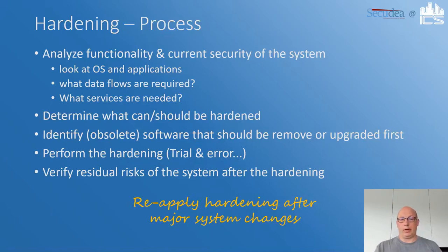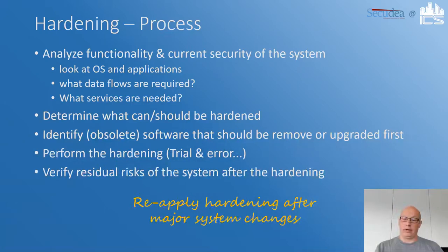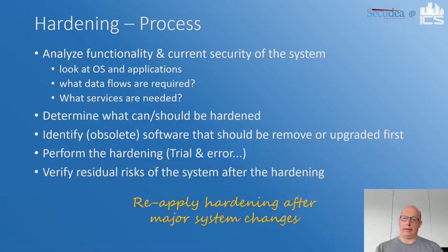After you do the hardening and everything is running, first verify the functionality of the system. Then it's also key to verify residual risks after hardening to make sure the system is as secure as possible and to identify what can be done with remaining risks. Whenever there are major system changes to the hardened system, verify whether hardening needs to be reapplied, because installing patches or application upgrades may require settings to be reapplied to maintain the known secure state.